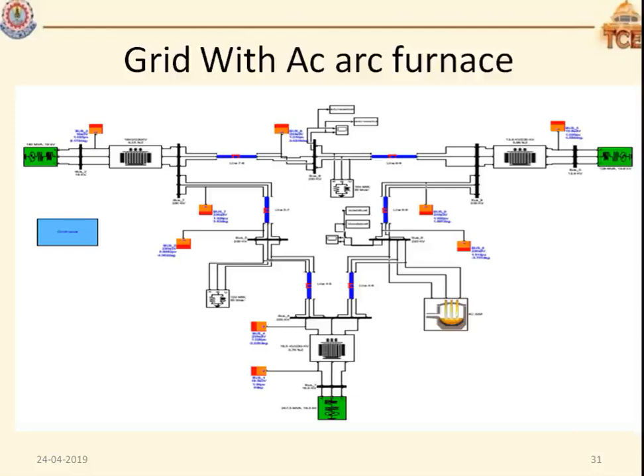Next, the second case is the grid with the AC arc furnace. Here at bus 8 we have placed the AC arc furnace, and we measure the power quality parameters such as voltage THD and current THD at bus 8 and at an adjacent bus such as bus 6, to see how an AC arc furnace connected as a load affects the adjacent buses. So we have taken the measurement at two different buses. The first bus is where the arc furnace is placed, and the second is the adjacent bus with reference to the arc furnace bus.